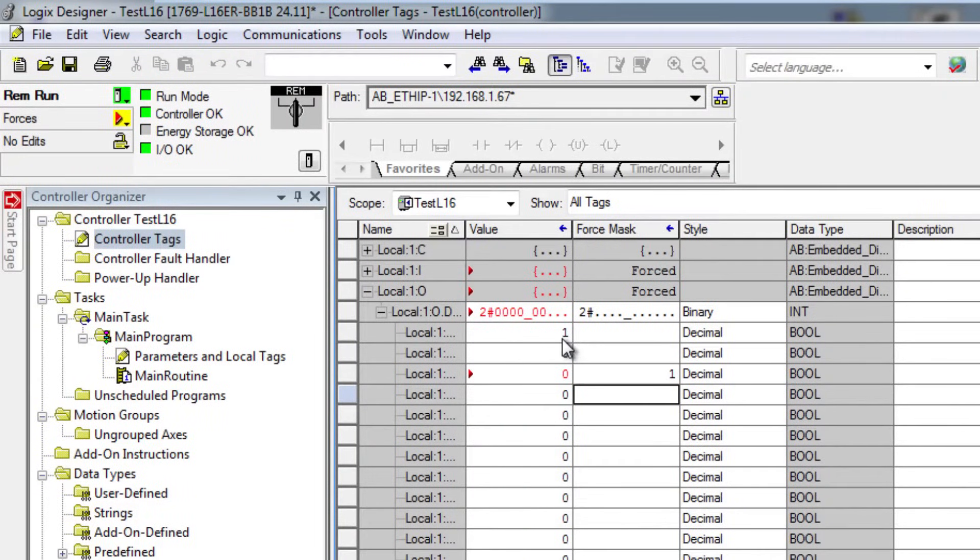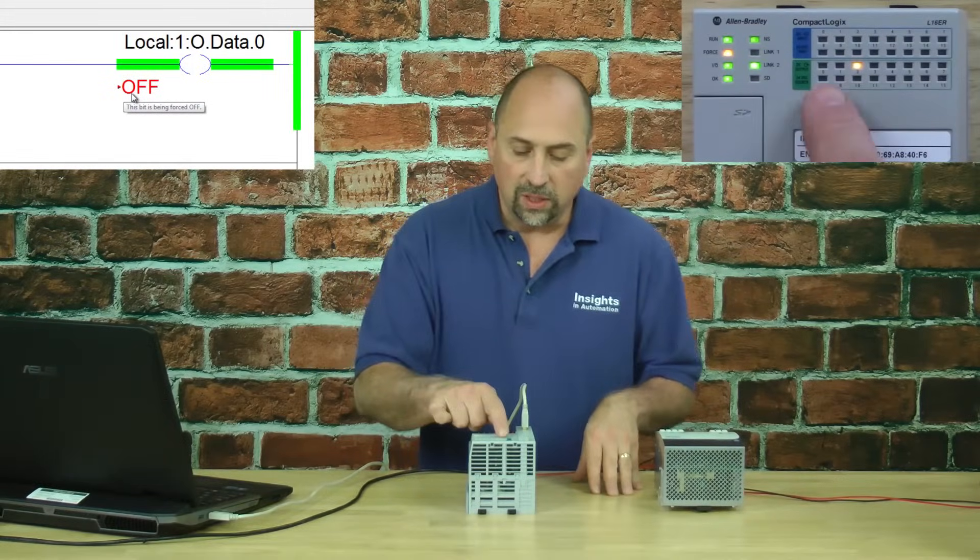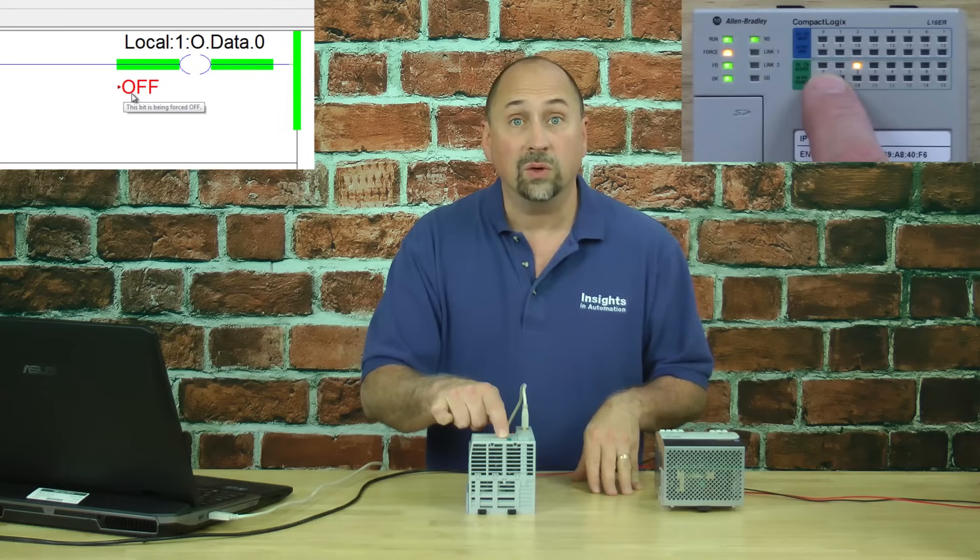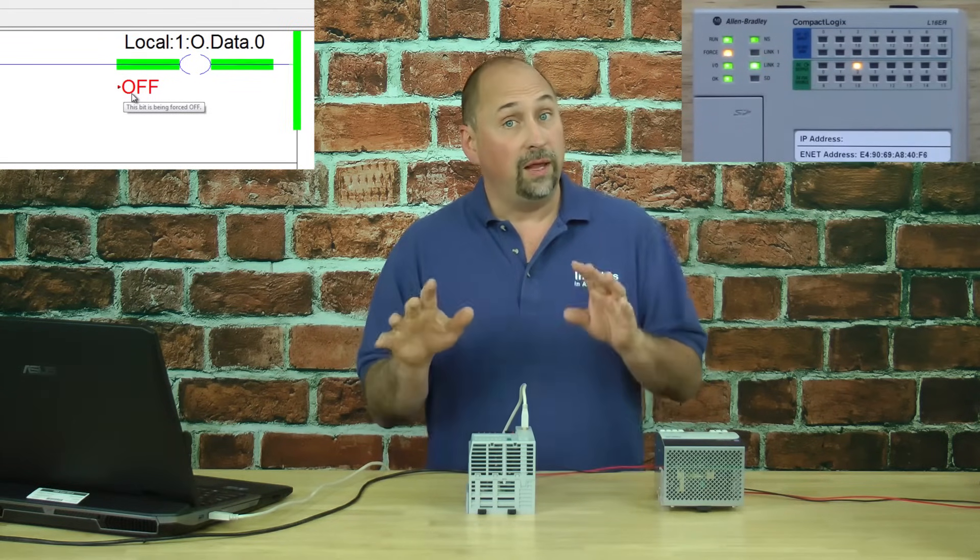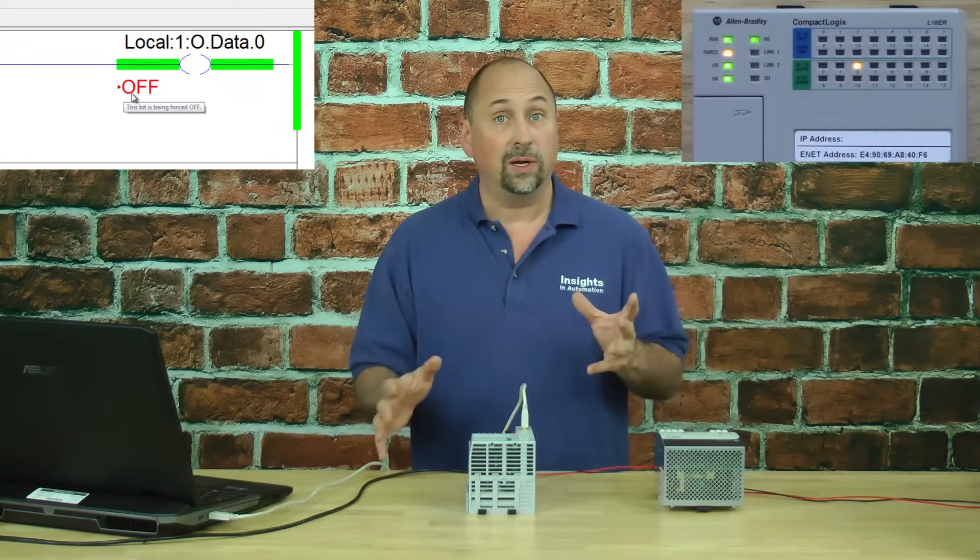We'll go back to the controller tags. I will put a 0 in the force table, and now if we look back at the controller, we can see output 0 has gone off, even though the program is telling it to turn on.